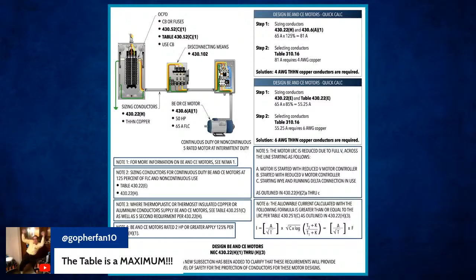Okay. So it says a protective device that has a rating or setting not exceeding the value calculated according to the values given in table 430.52(C)(1) shall be used unless otherwise permitted for the next size and maximum size, which is 430.52(C). Not a maximum size table, weed man. So I have a protective device rating or setting not exceeding the value calculated. So if I can't exceed the calculated value, then that means I have to drop down to the next standard size. Is that correct?